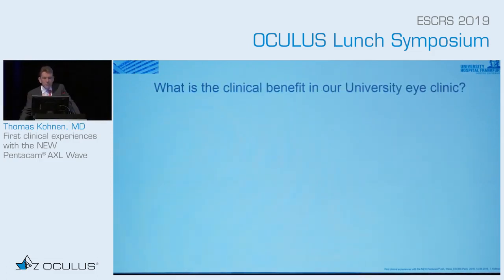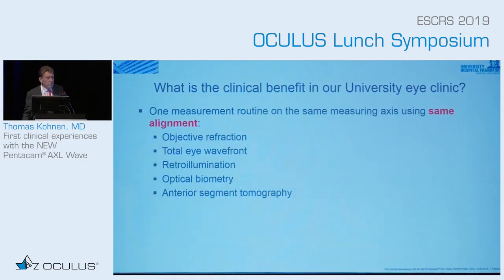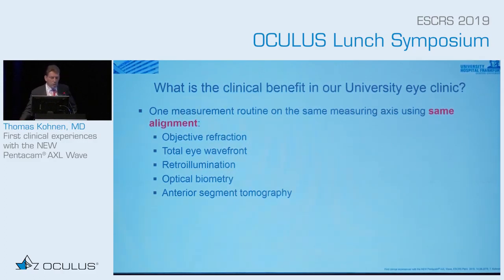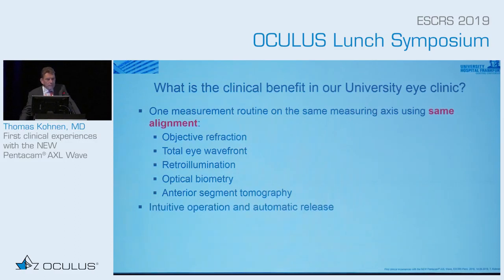What is the clinical benefit in our university? We've used this for the last several weeks and figured out that with one measurement routine on the same measurement axis using the same alignment — that's very important — you can get the objective refraction, total eye wavefront, retroillumination, optical biometry, and anterior segment tomography.